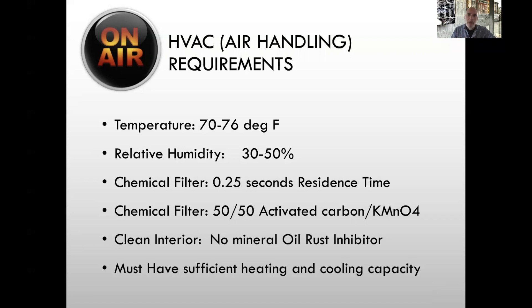The air handling system must provide a very stable climate — temperature and relative humidity in a narrow range — because the stability of the culture system is essential for success rates. The chemical filter needs a long residence time; 0.25 seconds is considered appropriate — the longer the better, though more expensive. The filter should consist of a 50/50 ratio of activated carbon and potassium permanganate, though other products and ratios are also used. The ductwork interior must be clean; no mineral oil rust inhibitors, and the system must have sufficient heating and cooling capacity.